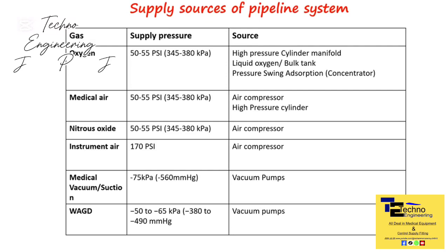Medical air is compressed air supplied by a special air compressor at a pressure of 4 bar. It is also called medical air 4 bar. In smaller facilities, medical air may also be supplied via high-pressure cylinders. Nitrous oxide is supplied by high-pressure cylinders. Some bulk systems exist, but are no longer installed due to environmental concerns. System pressures are around 50 psi.